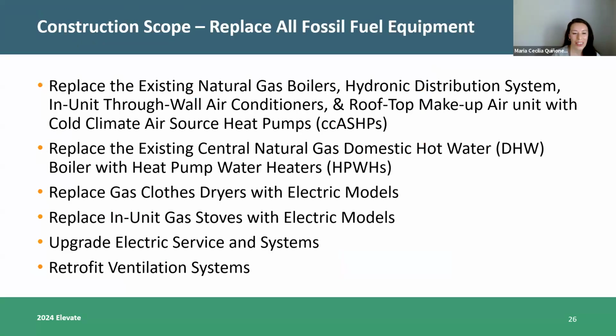Here's the construction scope. The goal was to fully electrify and replace all fossil fuel equipment. Focusing on the heat pump piece, we replaced the existing natural gas boilers, two of them from 1998, the hydronic distribution system, the in-unit through-wall air conditioners, and the rooftop makeup air unit, with cold climate air source heat pumps. Cold climate is the most important keyword in that description.